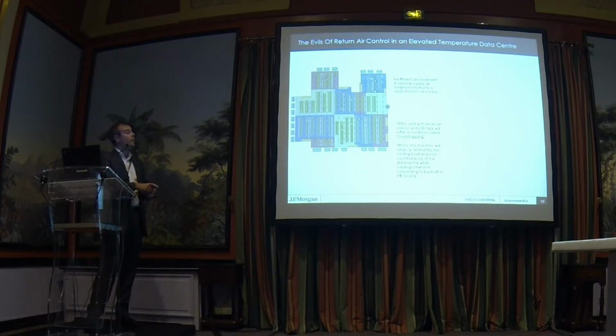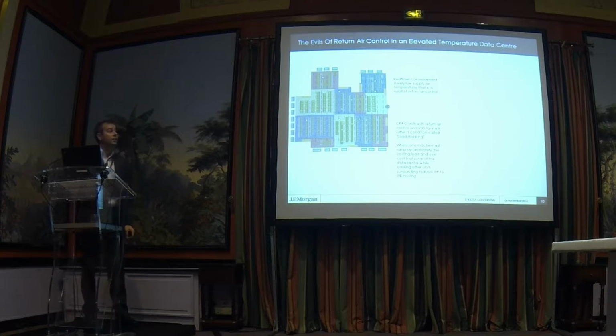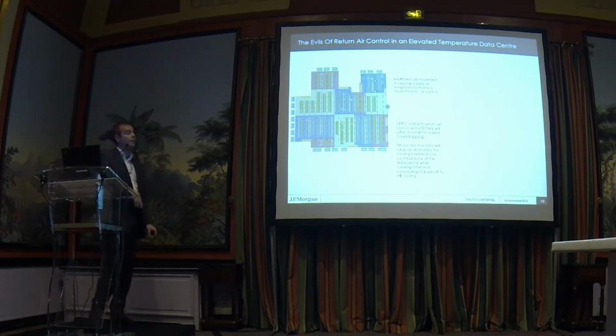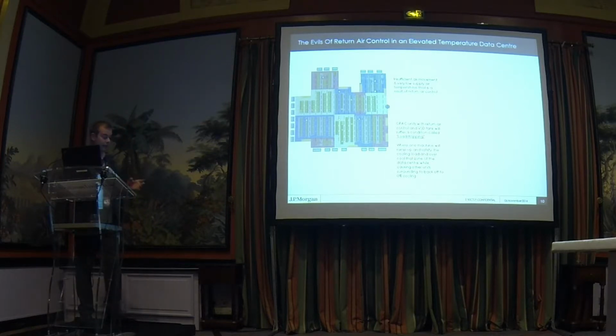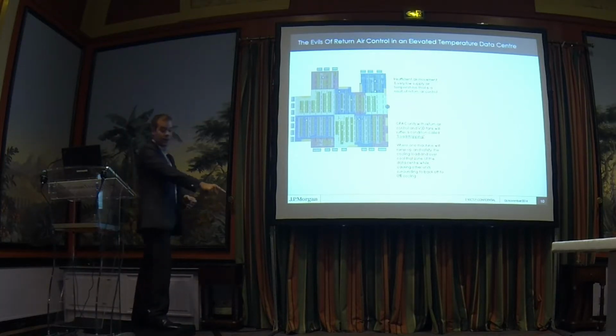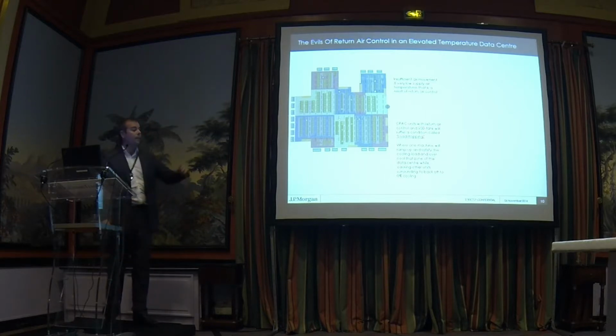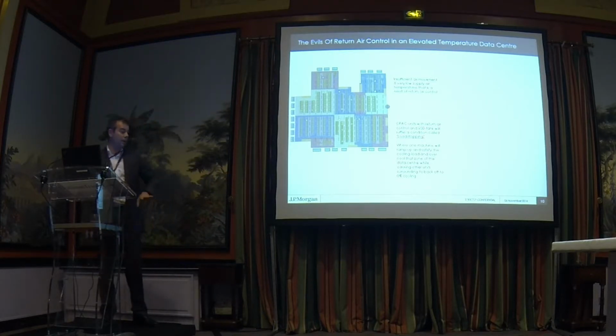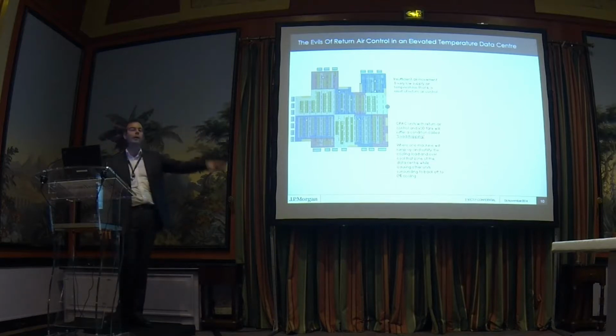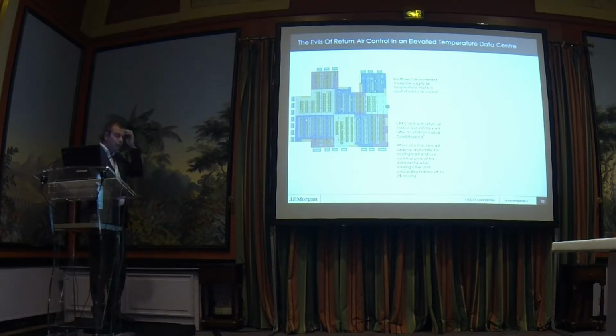So the other one here will read 24 degrees, so 23.9, set point at 24. The actual air conditioner will shut its valve. So 23.9 degree air will go into the CRAC unit, and then out the bottom of the CRAC unit will become 27 degrees. I could walk up the data center with a thermal camera, and I could basically see 15 degrees on the floor, and then I walk up a bit further, I see 26 degrees on the floor. There's a big red spot, big green spot, big red spot all the way along. And one machine at 100%, or 3 machines running at 33%, is less energy and less water movement.